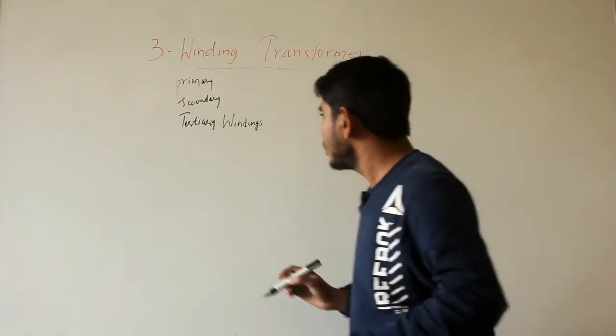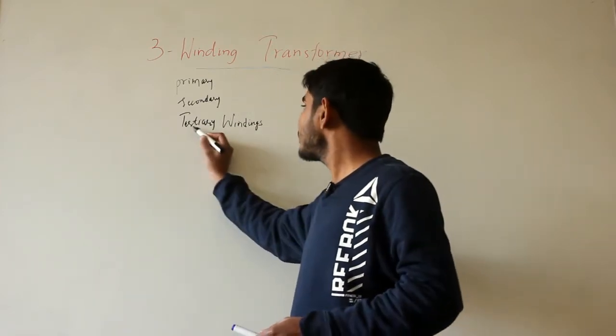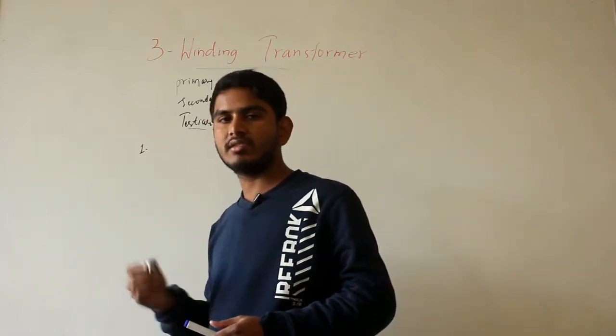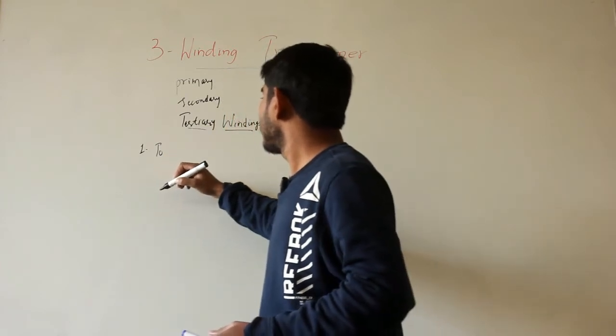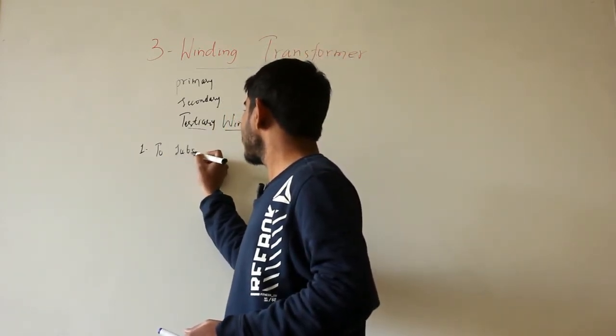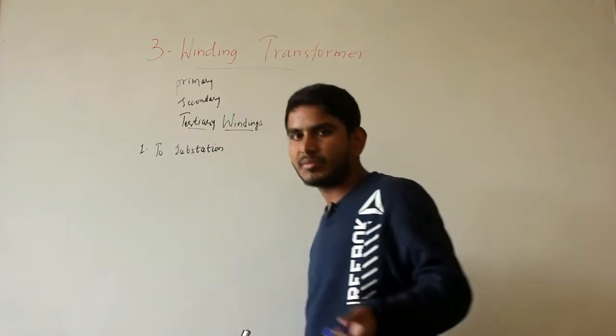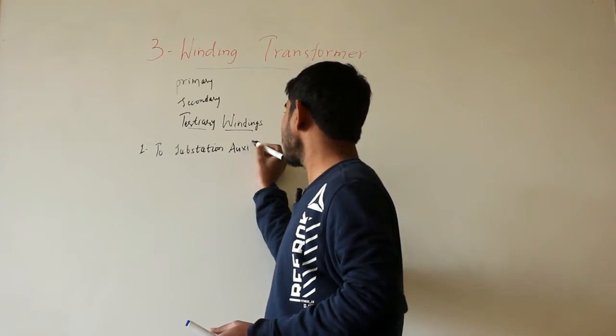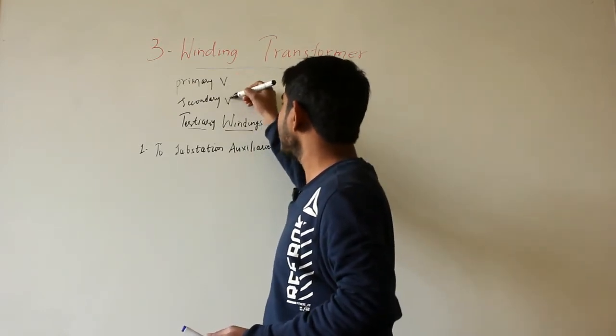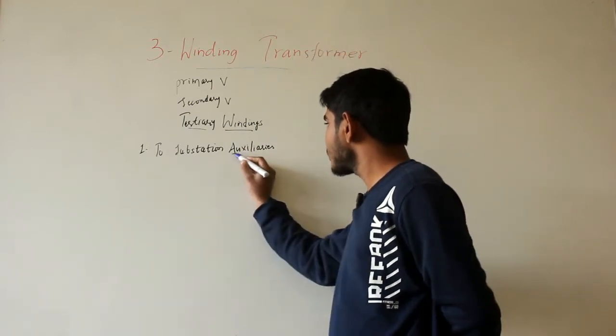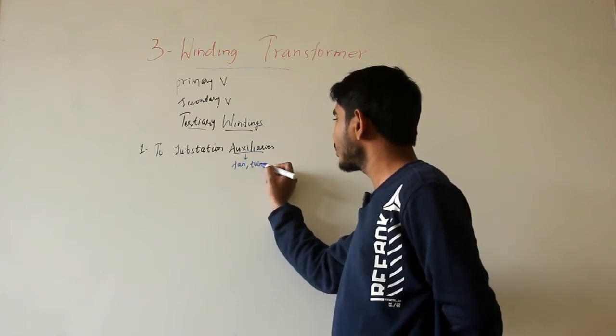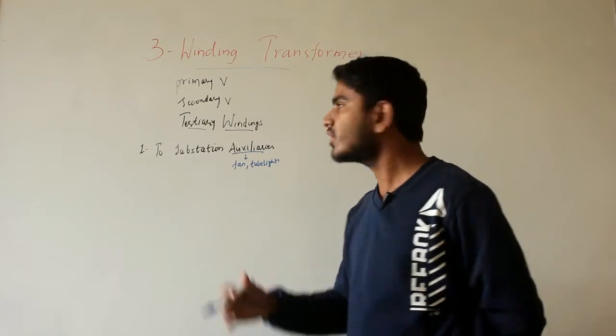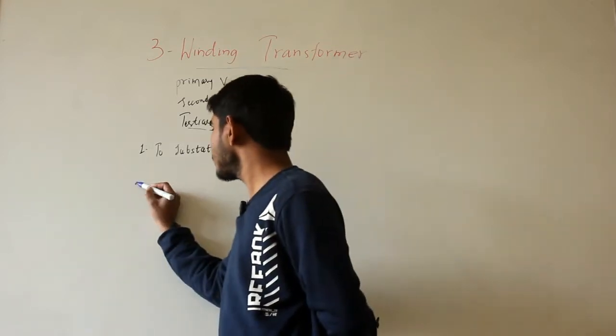The first purpose of employing a tertiary winding is that it can serve to supply the substation auxiliaries at a voltage which is different from the primary voltage and the secondary voltage. The substation auxiliaries may be fans, tube lights, and so on. So in order to supply these auxiliaries at a different voltage, the tertiary winding is used. The second purpose is to supply phase-compensating devices.